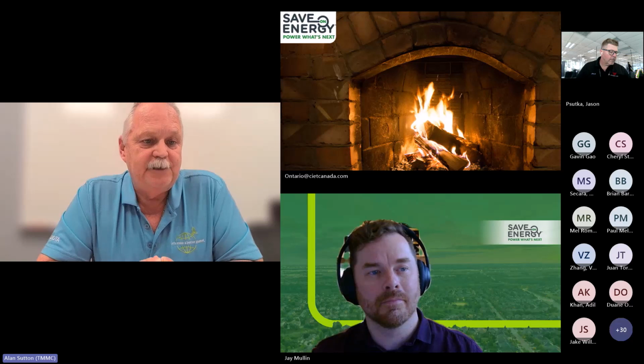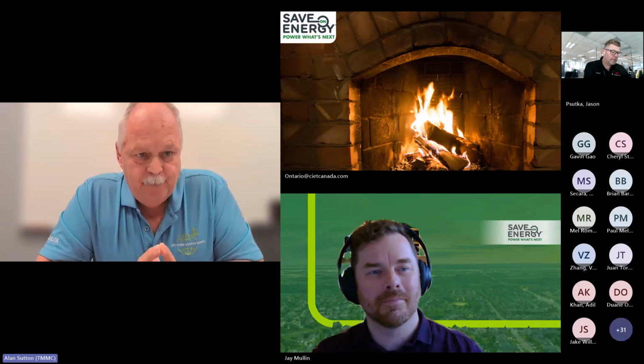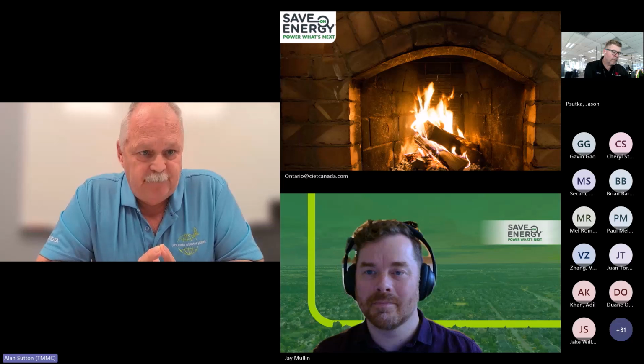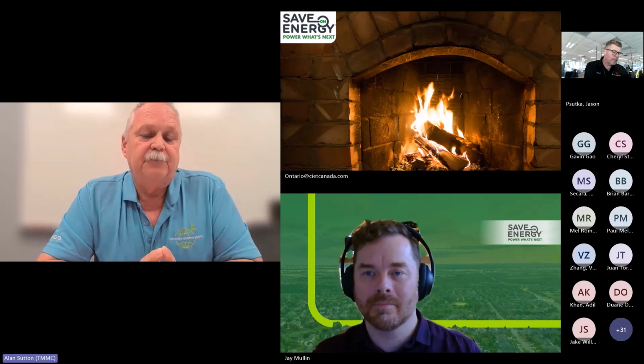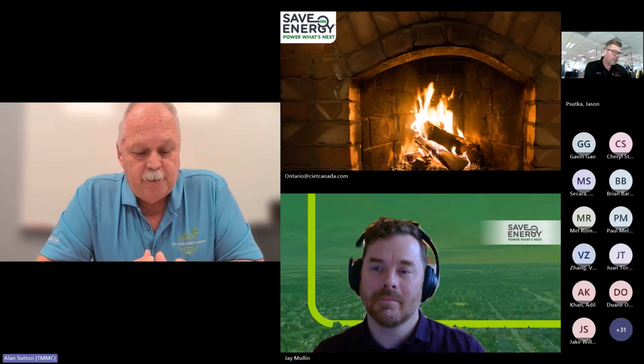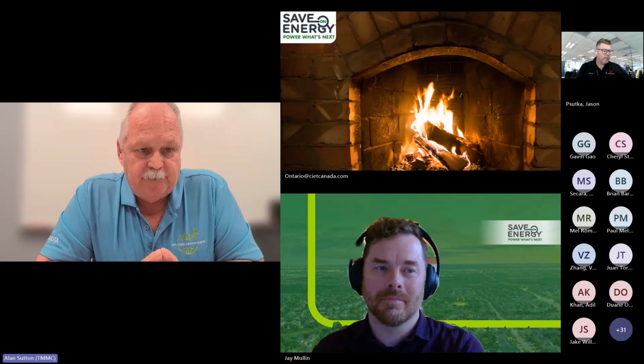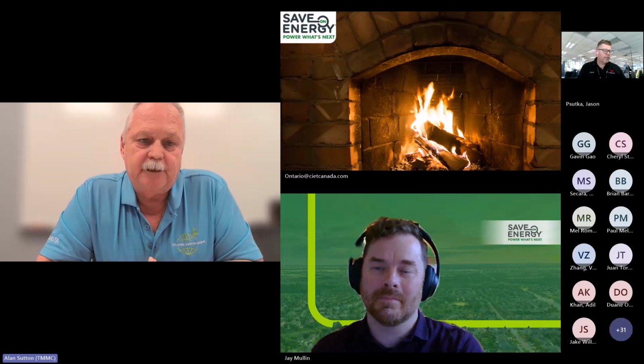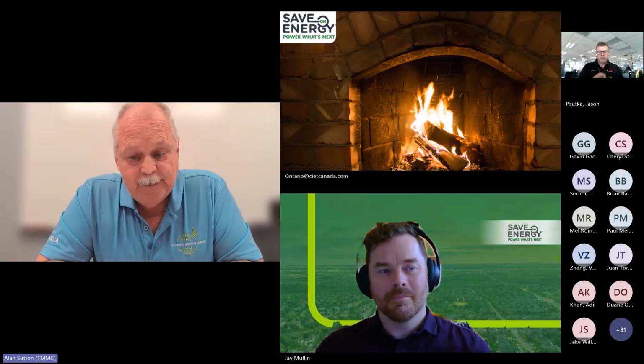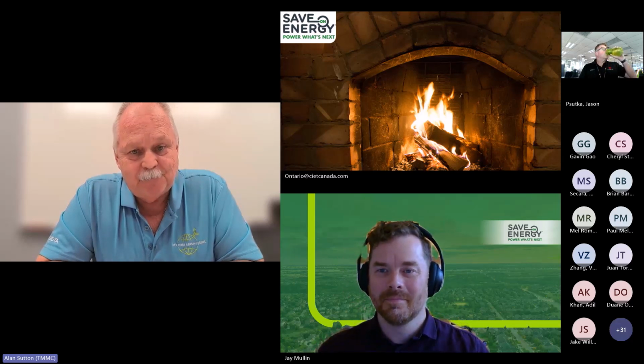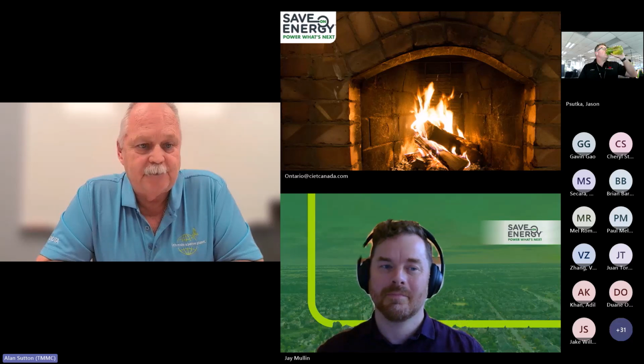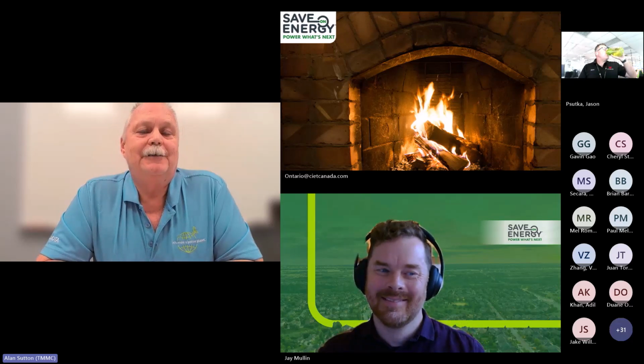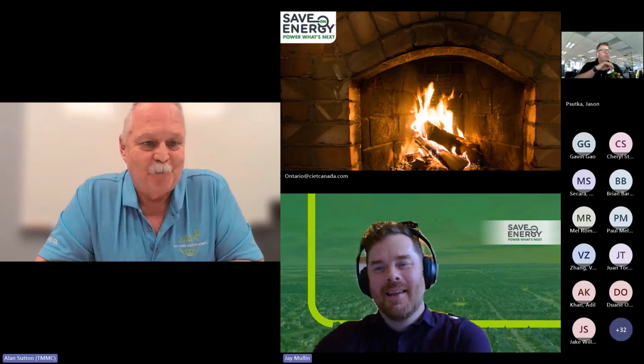One of them was a legacy issue: on this line we had 43 motors, and several of them had VFDs while several did not. As part of the energy audit, we dove deeper into data collection and the controls, looking at time of use and similar issues. What we found is the VFDs that were installed were never connected to the control system. I have no explanation of why that happened.